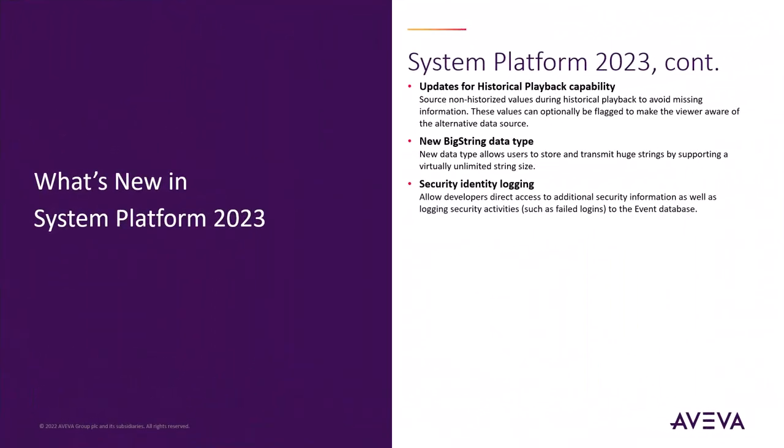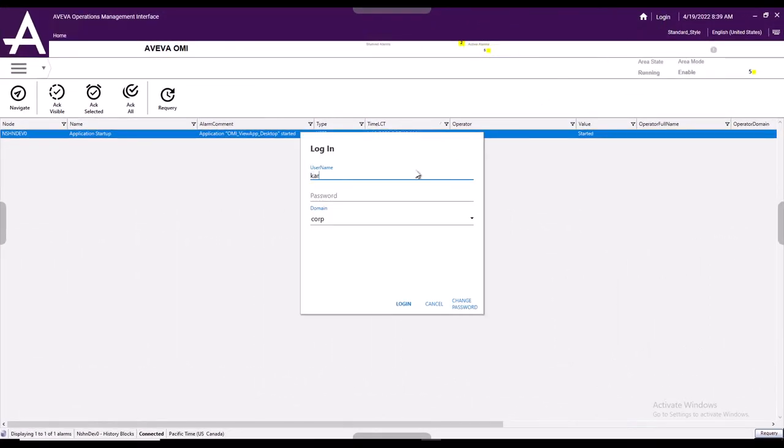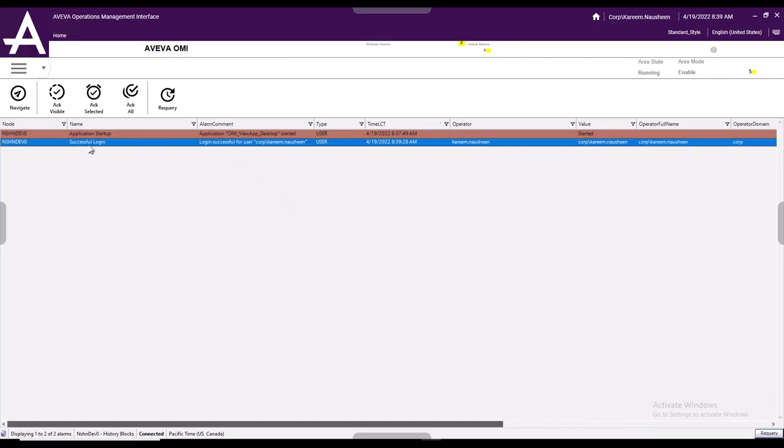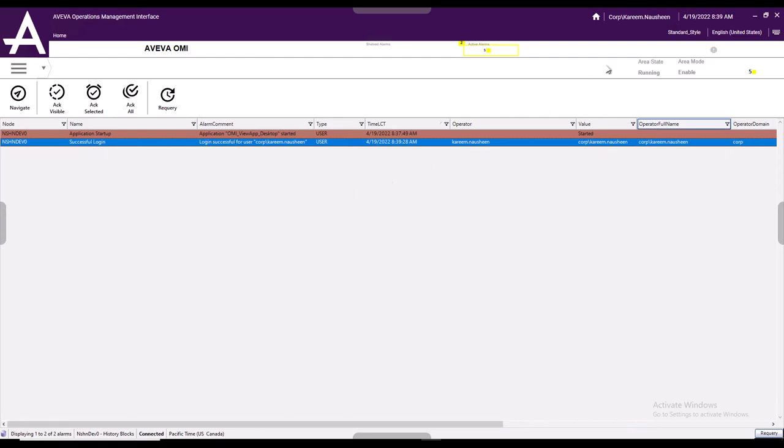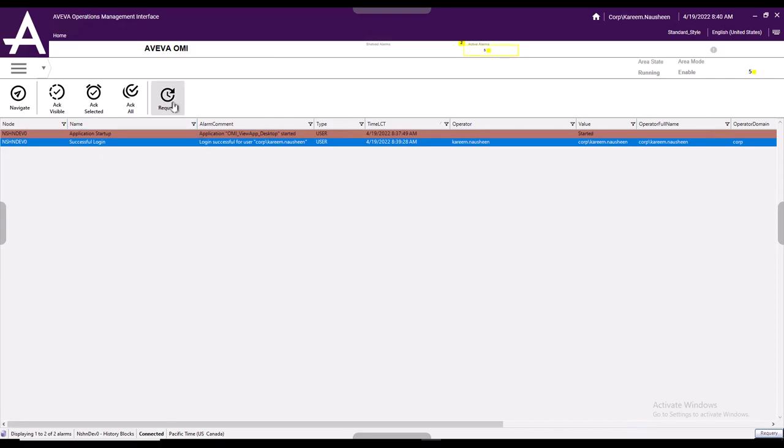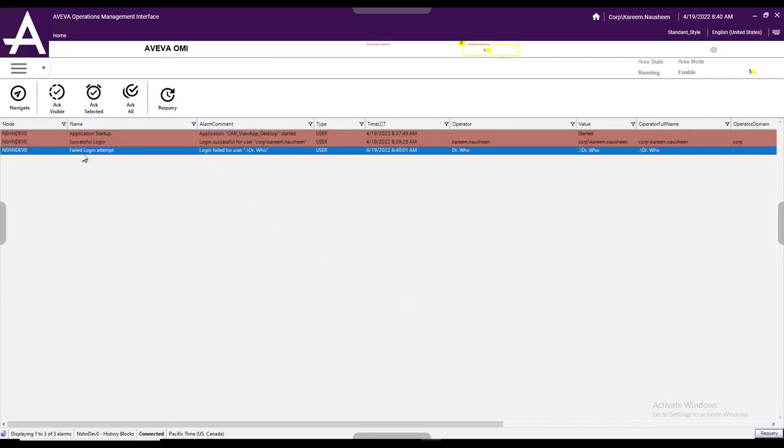Then we also added additional security event logging capability. In order to better comply with CFR 21 part 11 in our pharmaceutical industries in System Platform 2023, we are logging additional security information into the event subsystem. We now log an event whenever OMI starts up, and whenever a user logs in, that is also tracked in the event subsystem. And in the alarm and event history, we can see some additional information about the user that logged on. If a user attempts to log in and fails in his attempt to log in, whether that failure is because he provided a user that doesn't exist or an incorrect password was supplied, we will also track a log on failure event in the event subsystem for that.